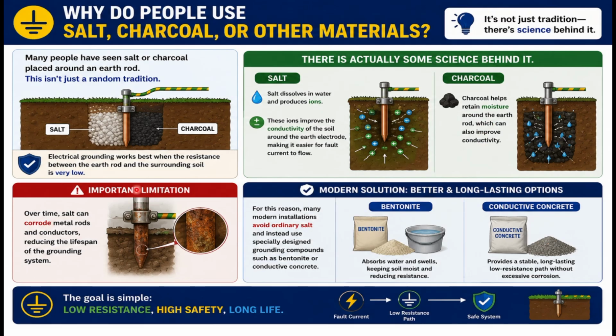And again, this solution we are bringing to solve the problem of resistance also comes with a limitation, right? Over time, salt can corrode metals and conductors, reducing the lifespan of the grounding system. So you can see this earth rod is corroded, and that is one of the limitations of this. In order to counter this situation, this is where we have bentonite. Many installations avoid using ordinary salt, and they use instead specially designed grounding compounds such as bentonite or conductive concrete. Bentonite absorbs water and swells, keeping the soil moist and reducing the resistance. And conductive concrete provides a stable, long-lasting, low-resistance path without excessive corrosion. So this is the explanation for that.